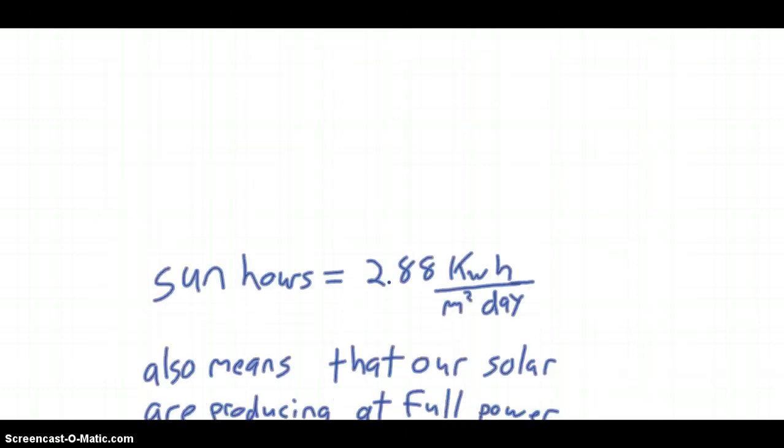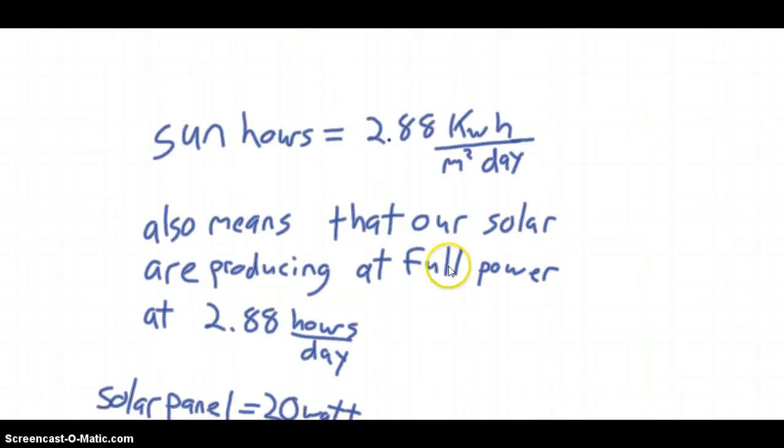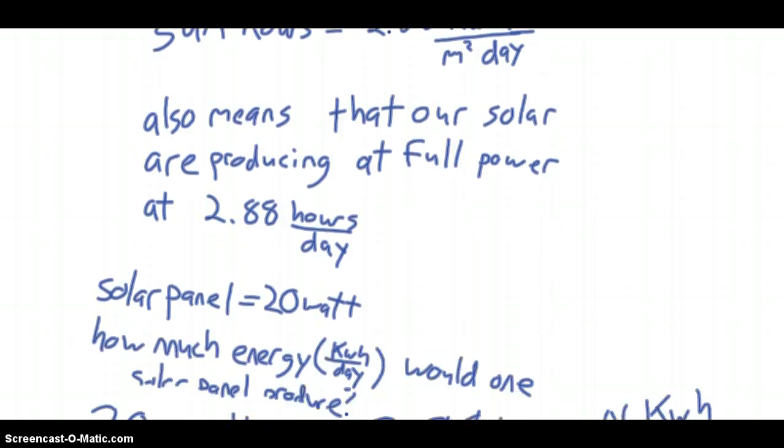And if we go down to the next, sun hours also mean, that we have our 2.88 from above, but it also means that basically our solar panels are producing at full power for about 2.88 hours per day. So it's just an equivalent measure. It doesn't mean they're actually only producing for 2.88 hours, and they're producing at max power. If it's a little cloudy for six hours, and they're producing at half, then they might be producing equivalent of 2.88 full hours that day.